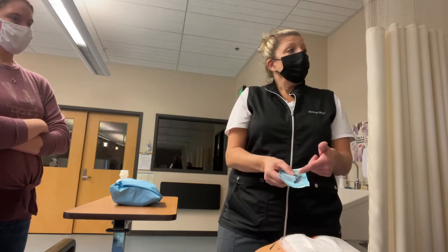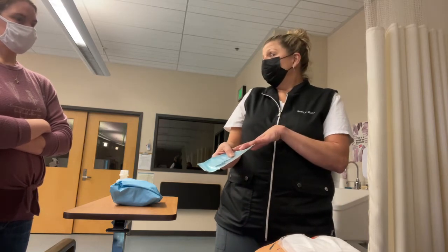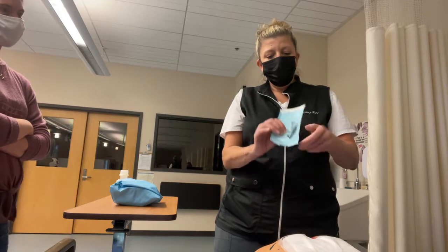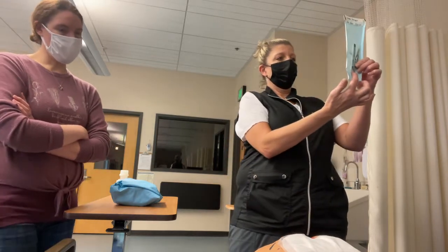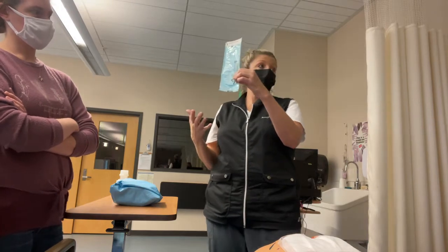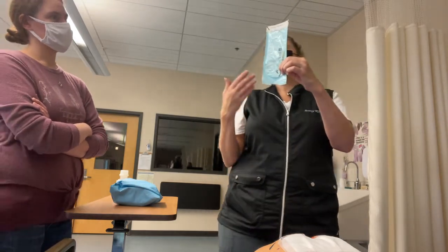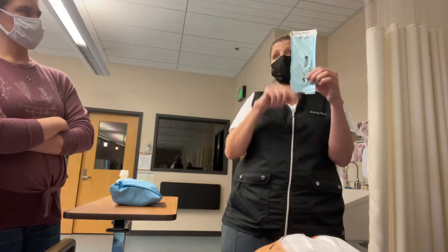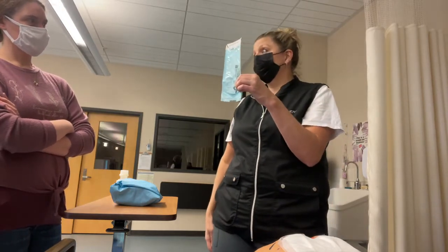We want to make sure that the inside is sterilized. So obviously the outside reached it, but the inside we want to make sure too. So this check mark right here, when we put that strip in before we sterilize it, is blue. The sterilization process, going through time, temperature, and pressure, turns it black. So now I can be sure that the instrument on the inside is sterile.